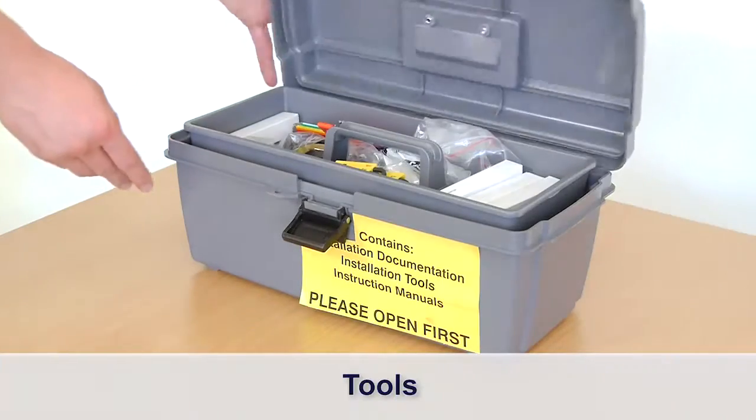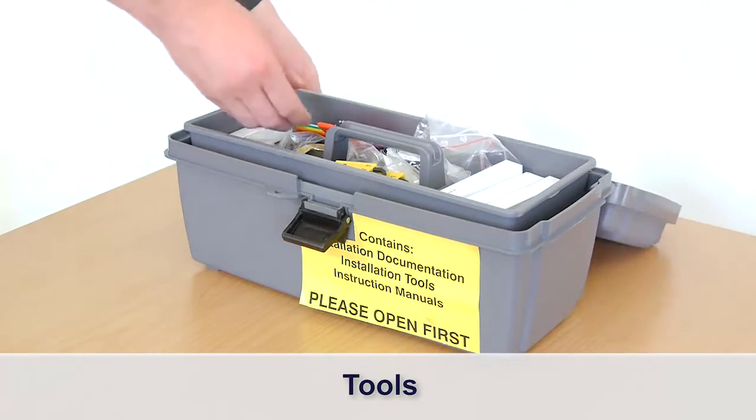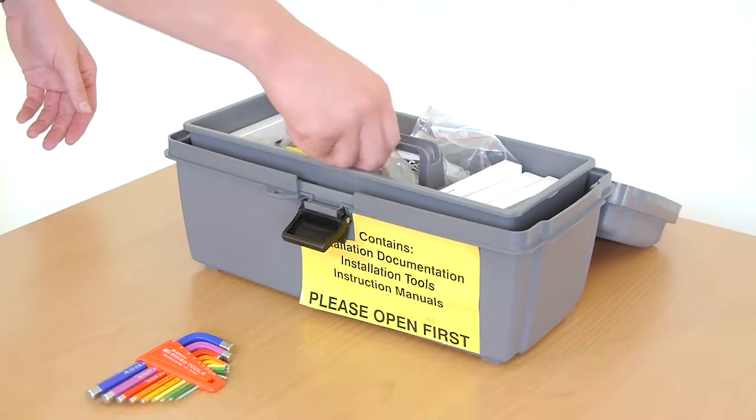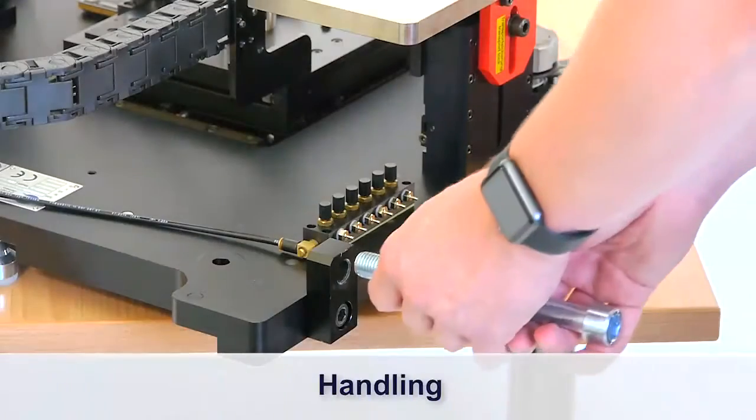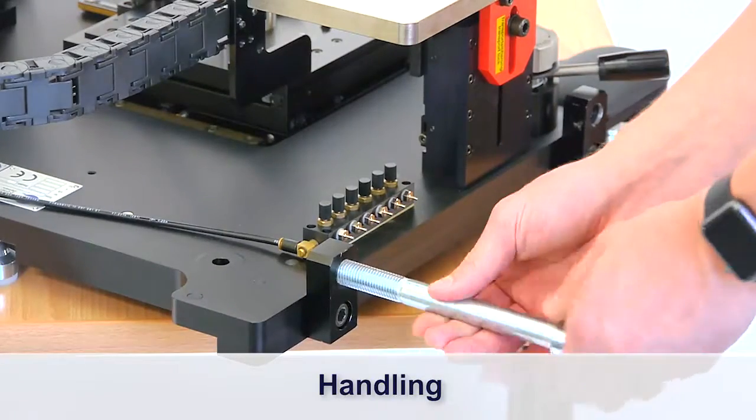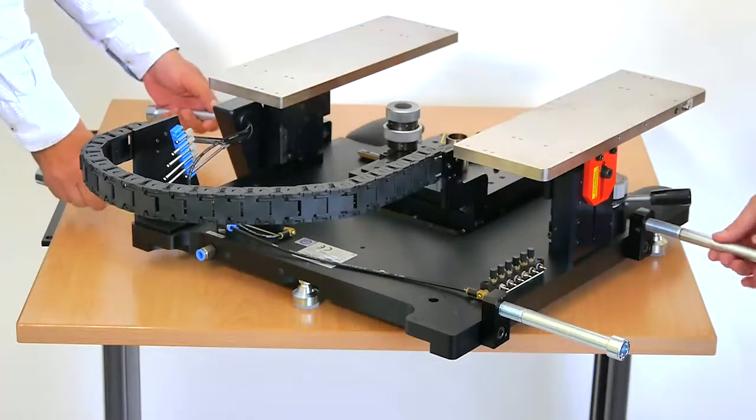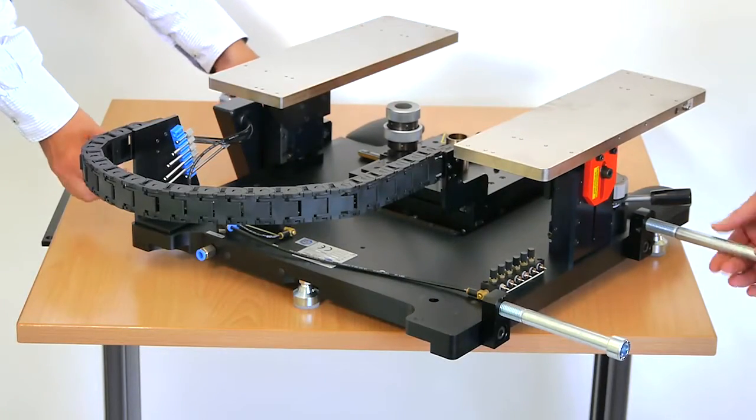After unpacking the probe system, open the delivered toolbox which consists of everything you need for setup. It is mandatory to install the lift handles and use them for placing the probe system. Be aware that the system must be handled with one person at each side.